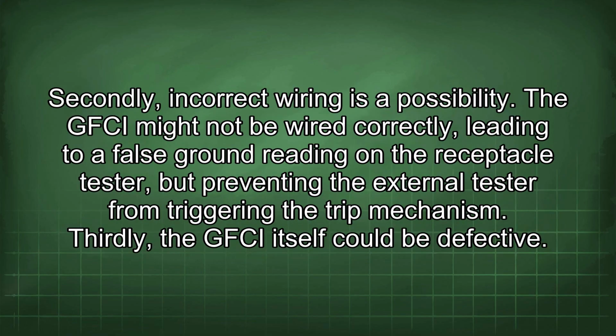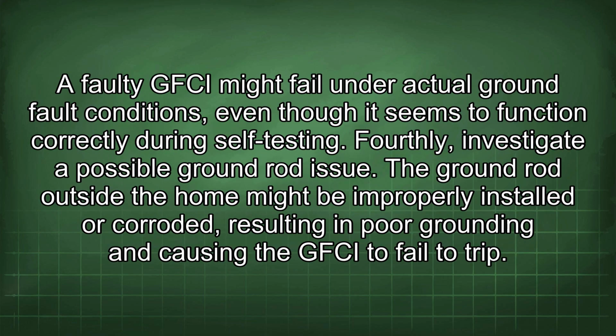Secondly, incorrect wiring is a possibility. The GFCI might not be wired correctly, leading to a false ground reading on the receptacle tester, but preventing the external tester from triggering the trip mechanism. Thirdly, the GFCI itself could be defective. A faulty GFCI might fail under actual ground fault conditions, even though it seems to function correctly during self-testing.